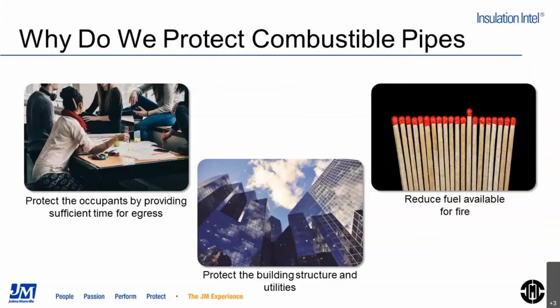So from the high level, with these pipes in the plenum potentially, why would we need to protect them? Again, because there's an air movement between the plenum space and the occupiable space, we really want to give the occupants time to egress in case of a fire. By having the combustible pipes protected and limiting combustibles, that's how we will achieve that.